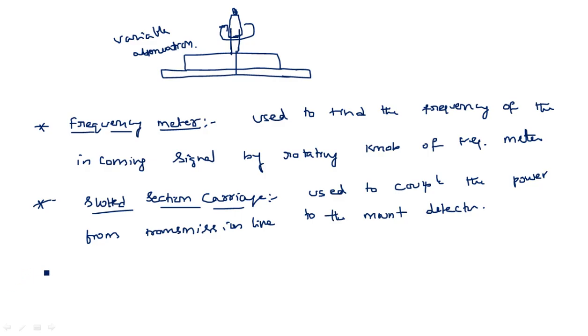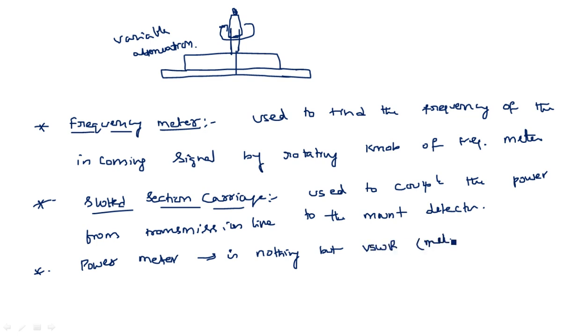After the detector mount, we have a power meter — also called a VSWR meter. The VSWR meter detects both VSWR and power. There are two types of readings on the meter: the VSWR reading and the power reading, shown in red. Depending on what measurement is needed, you select the appropriate reading from the VSWR meter.